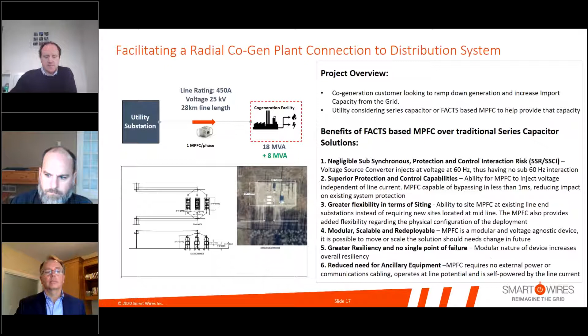A couple of benefits that come to mind: negligible subsynchronous resonance issues with a FACTS-based power flow controller versus a series cap, and greater flexibility in terms of siting and resiliency. With modular solutions, there's no single point of failure—if a device fails, you don't lose your entire solution, unlike traditional series capacitors, series reactors, or phase shifters. This is typical in Alberta and Canada generally, where cogeneration facilities and mining loads are located at the end of radial feeders, and a power flow control solution can help facilitate requests for increased or decreased demand.